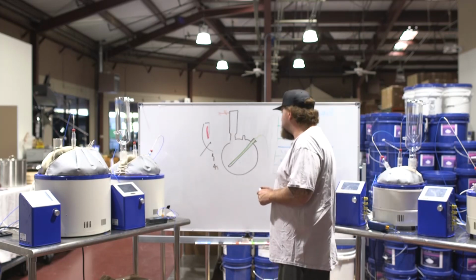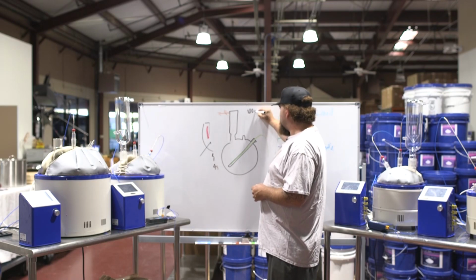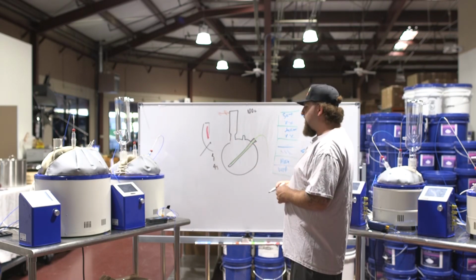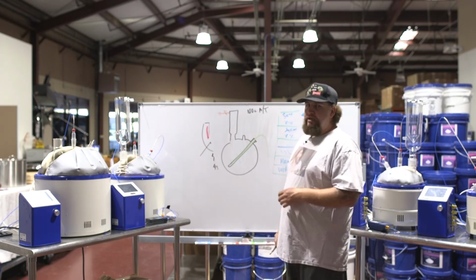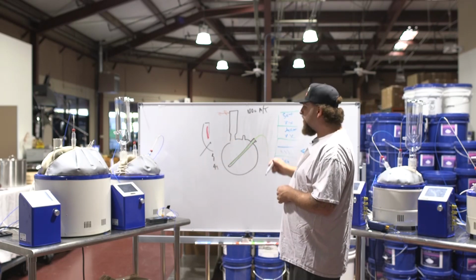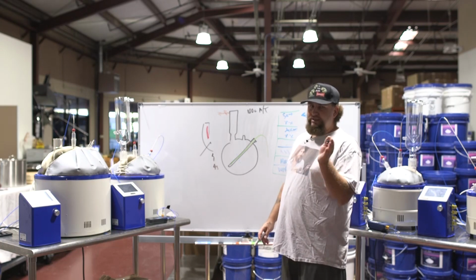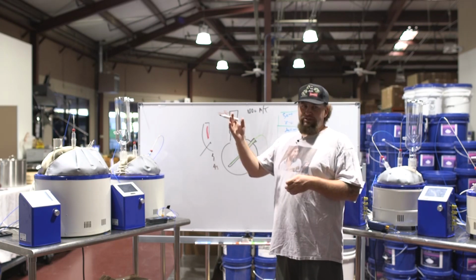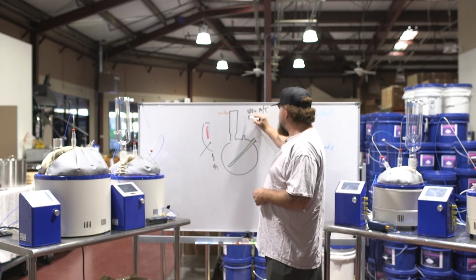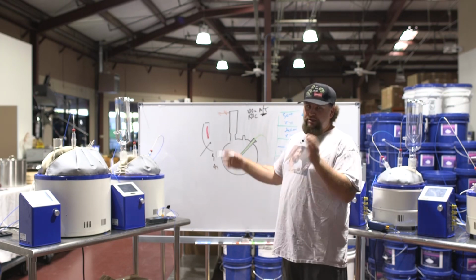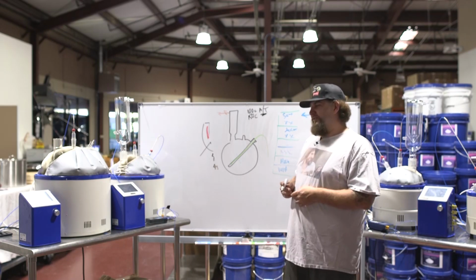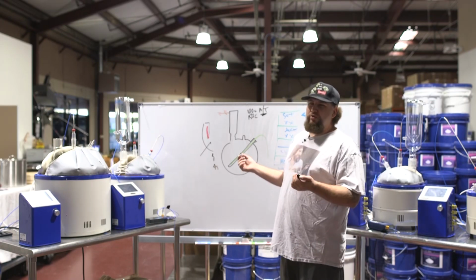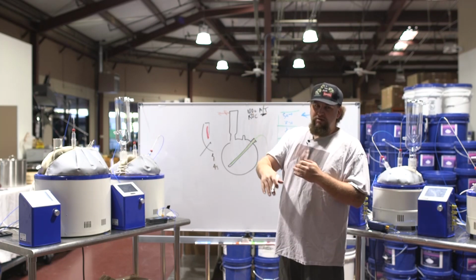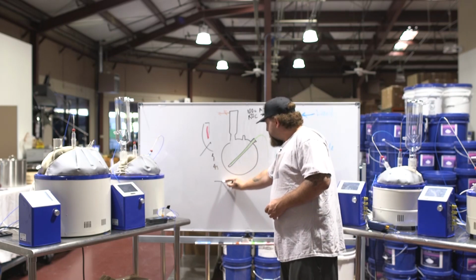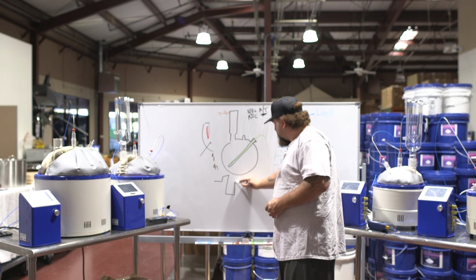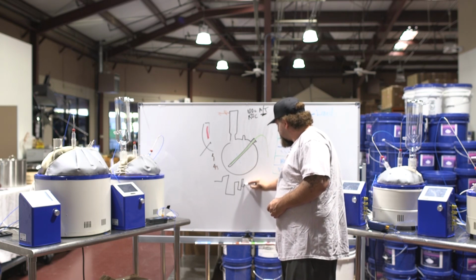So what I will do is turn the system on, and I will first just go to 100 Celsius with a liquid probe in there, and all the biases are set to 0, and I just go straight to auto tune. So I press auto tune immediately. That brings the jacket and the bowl up there. Once it hits 100, it goes back and forth and becomes a little bit useless, but you just want it to get to where it needs to go. So right around the time when it hits 100, I'll go straight to 150, and it's still doing the auto tune sequence. I let it just do its thing. It'll go up and down, and at this point it can take quite a while. I've seen some of the larger mantles take 4 to 6 hours to complete this. In a cooler room, it's a lot less, because it purposely goes up and then down, then up and down. It basically runs a circuit where it comes up and gets smaller and smaller, etc.